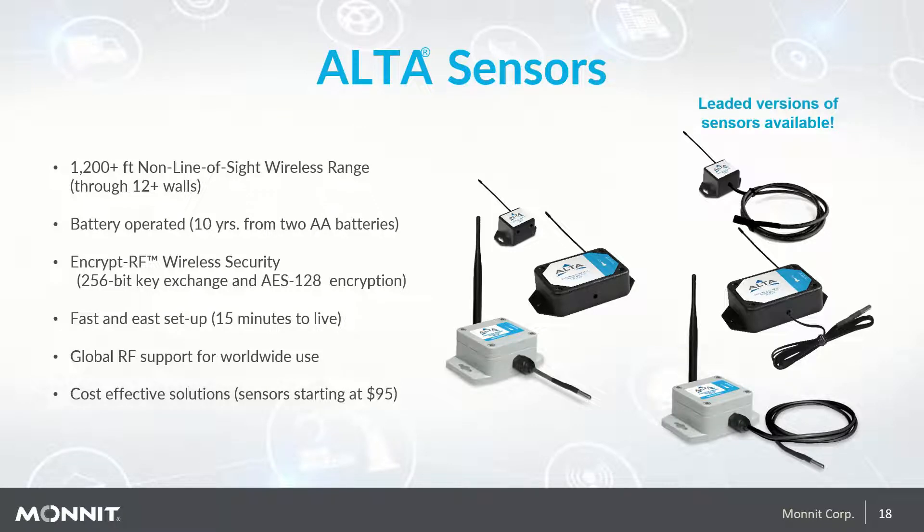Monnit Alta sensors offer best-in-class performance. Features include 1,200-foot non-line-of-sight wireless range, allowing monitoring through about 10 to 12 walls, an average battery life of 10 years for our AA sensor type, and bank-grade encryption for sensor data transmissions from the sensor to the gateway. Fast and easy setup in as little as 15 minutes, global RF support for worldwide use, and sensors starting at $95. Our sensors also include onboard non-volatile memory, so in the unlikely event of a transmission interruption, data is stored on the memory chip inside the sensor. When the connection is re-established, the data is uploaded in chronologically correct order and no data is lost — which is especially important in regulated industries.